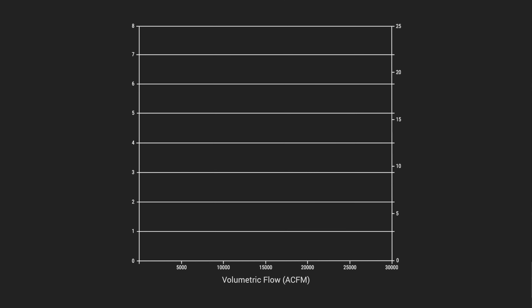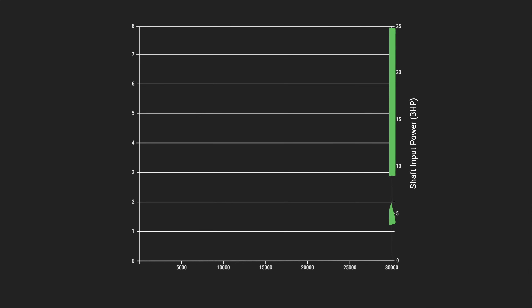Airflow is plotted along the x-axis at the bottom of the curve, often quantified as cubic feet per minute. Static pressure is plotted along the y-axis on the left side of the curve, commonly quantified as inches of water gauge. Power consumption is plotted along the secondary y-axis on the right side of the curve. You can reference our previous videos about fan laws for common metric units of measurement for each of these axes.